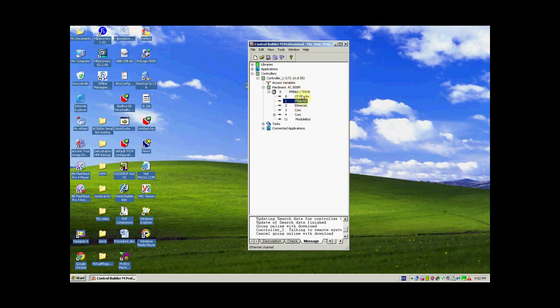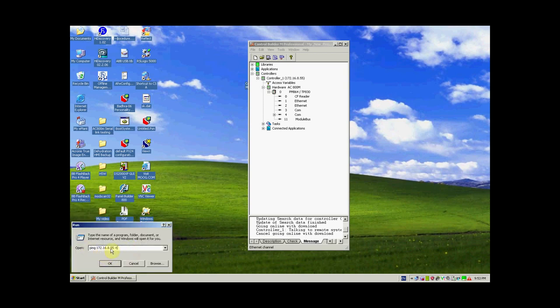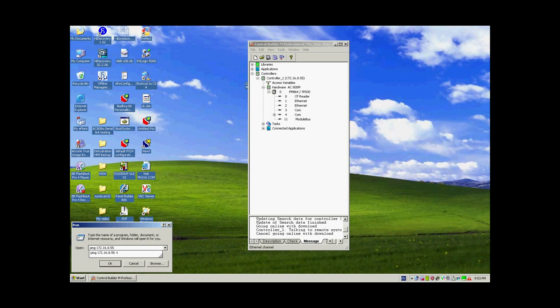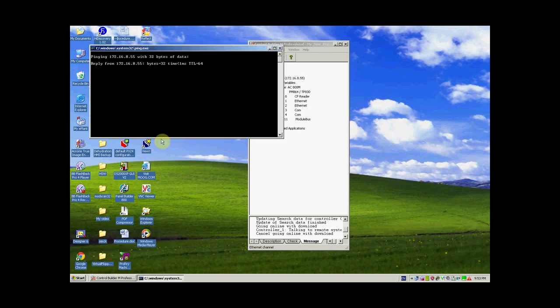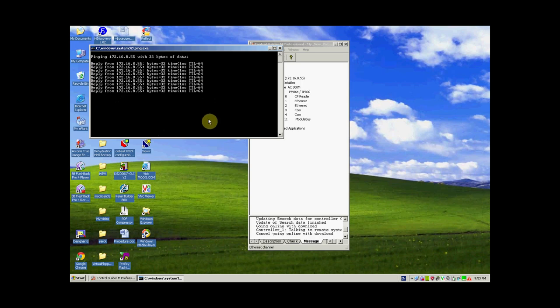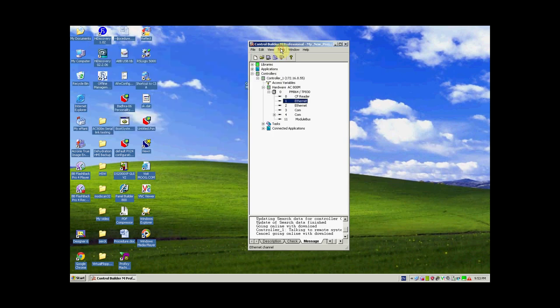We are now ready to communicate with the AC800M controller over ethernet using CN1. Connect the ethernet cable to CN1 and verify the connection is established. Go to Start, Run, and type PING 172.16.8.55 — the address of our controller. We have got successful replies from the controller, meaning our PC is communicating with the controller successfully.